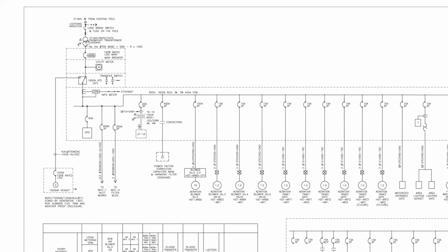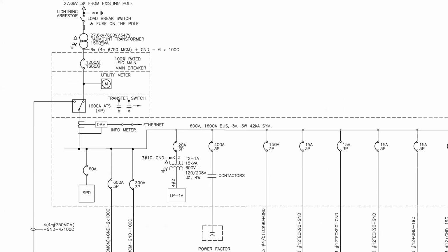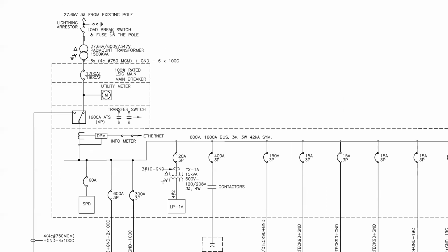Here's another example of how you could find a transformer. So instead of those funny loops, this is showing another 27.6 kV to 600 volt and 347 volt pad mount transformer, 1500 kVA. So pad mount transformer versus pole mount transformer versus wall mount transformer. I believe this is delta Y. And then it's listing the conductors, 6 times 4C, 750 MCM plus grounds. So this would be used for the electrician, the general contractor, or the electrical contractor to know how many and what power feeds to pull from the transformer into the main building.